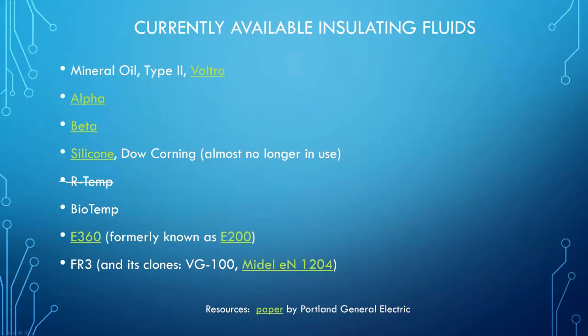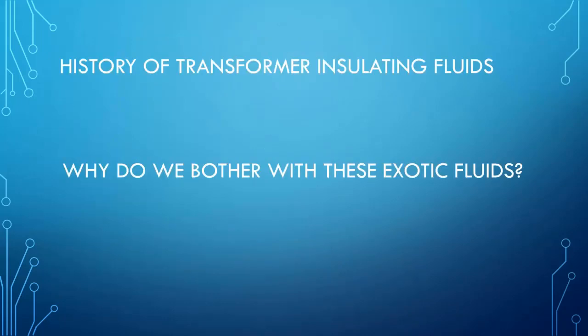Silicone is just not seen that much anymore. We get almost no requests for that. It had its place and had its day, and it is an effective transformer insulating fluid. It has high dielectric strength and a high fire point, but it is very, very expensive to dispose of. I did include a link here to the Dow Corning website, so you can read about silicone on your own time. But we do not see that specified very much anymore at all.